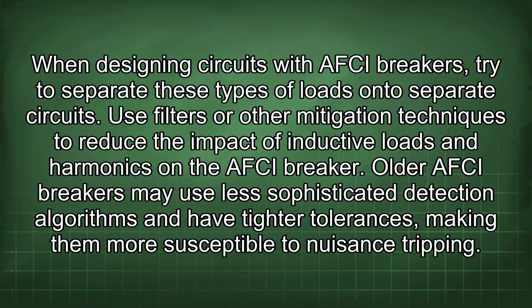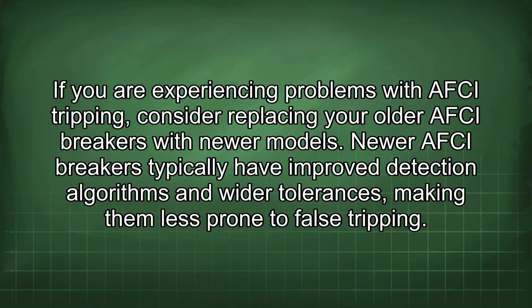Older AFCI breakers may use less sophisticated detection algorithms and have tighter tolerances, making them more susceptible to nuisance tripping. If you are experiencing problems with AFCI tripping, consider replacing your older AFCI breakers with newer models. Newer AFCI breakers typically have improved detection algorithms and wider tolerances, making them less prone to false tripping.